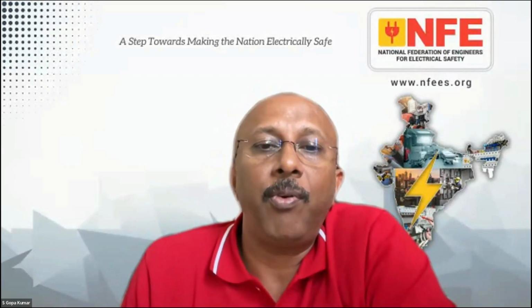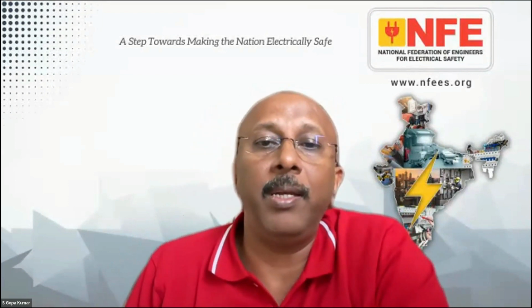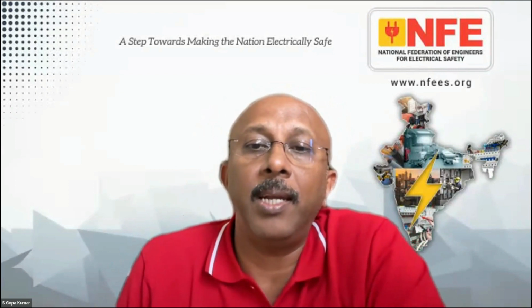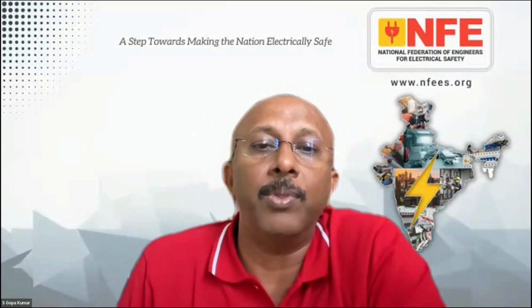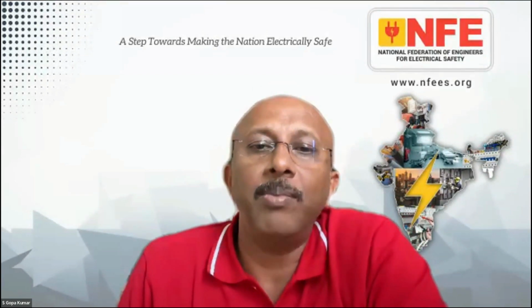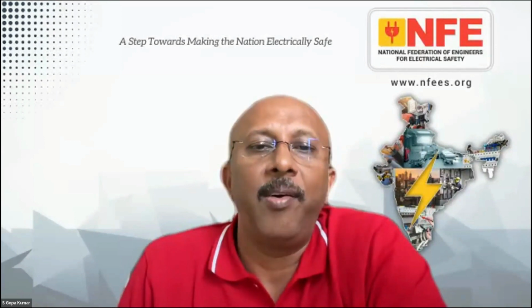Mr. Giridhar: for a 100 kVA distribution transformer, LT side current is around 131 amps. What size of MCB, MCCB, fuse shall we select? Well, that depends entirely on the cables and the loads. You will have to perform the analysis. It's not a simple yes or no answer.